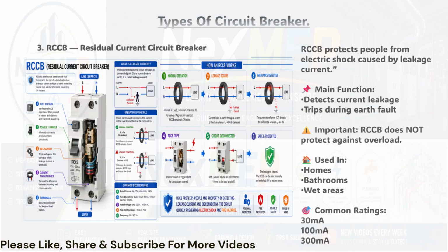The RCCB continuously monitors this difference using a current transformer. The moment it detects an imbalance, even as small as 30 milliamps, it trips instantly, disconnecting both live and neutral. This happens fast enough to prevent fatal electric shock. Important note, an RCCB does not protect against overloads or short circuits. That's not its job. It only detects leakage current.